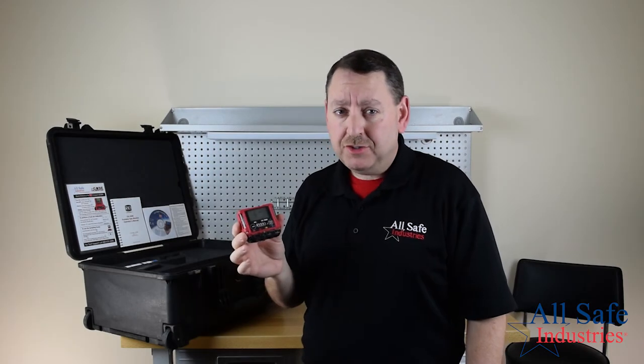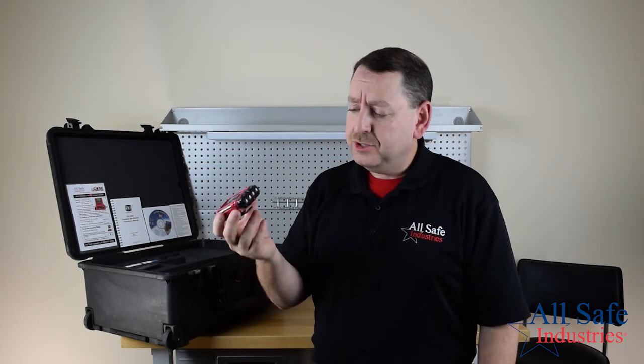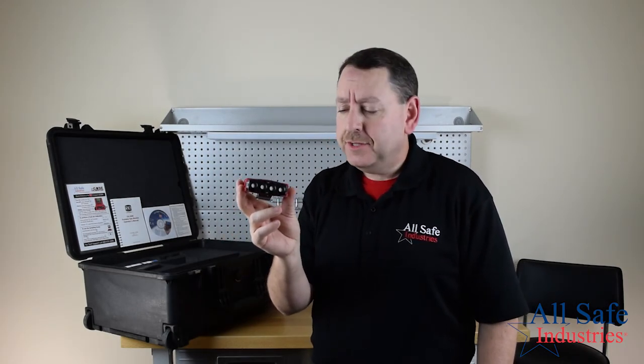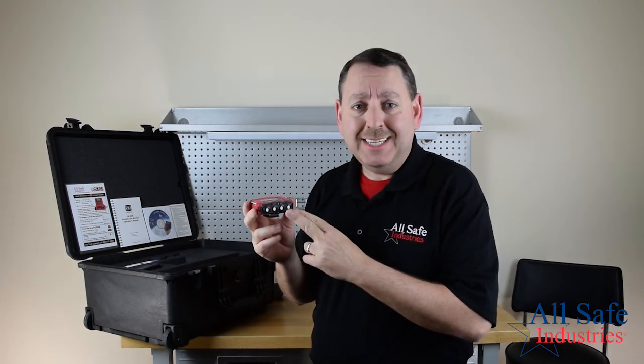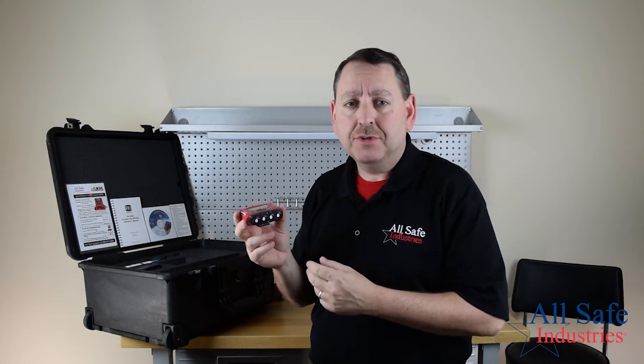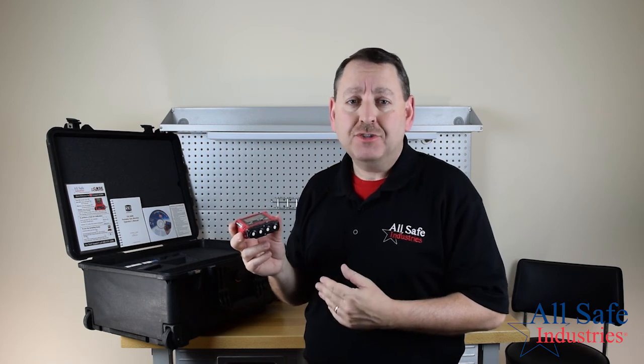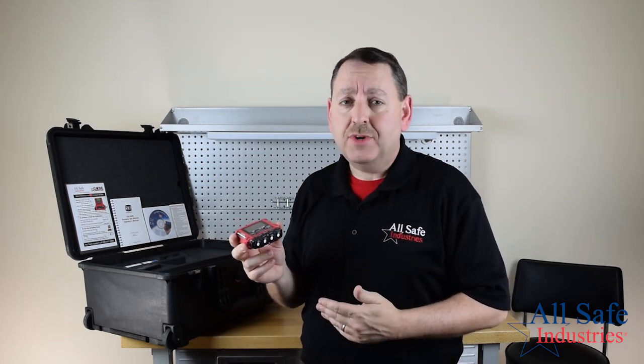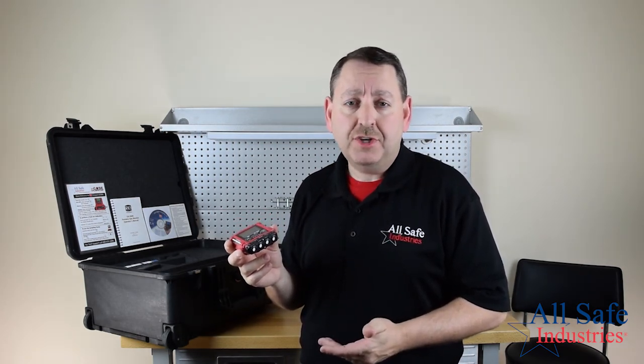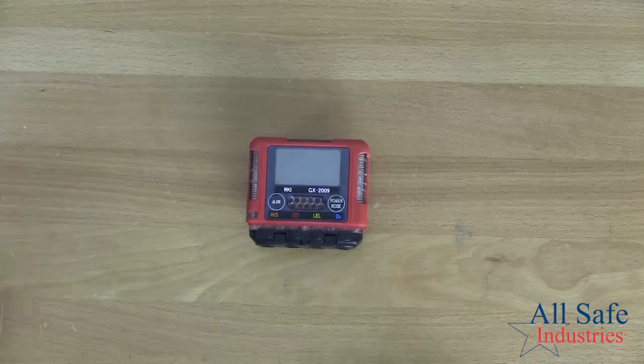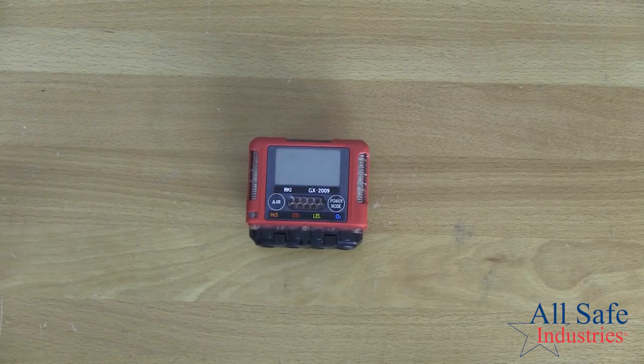Now we'll talk about maintenance on the GX-2009. The 4 sensors are located in the bottom of the unit. We have an oxygen sensor, an LEL sensor, or your flammable gas sensor, carbon monoxide, and hydrogen sulfide. Those sensors won't last forever, so when they wear out, they'll need to be changed, and I'll show you how to do that. All right, now we're going to do some maintenance on our GX-2009.